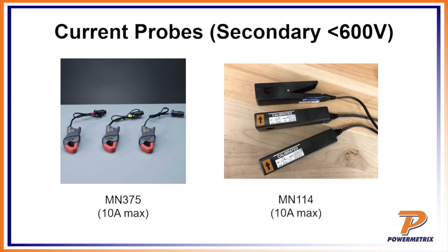So you can use those MN353s. They're actually the same size as the 375, so they're good and convenient. They're small, got a little smaller aperture, but they're easier to get in the cans. They are rated all the way up to 200 amps, so that means we can get up into the self-contained stuff in 2S's with those.